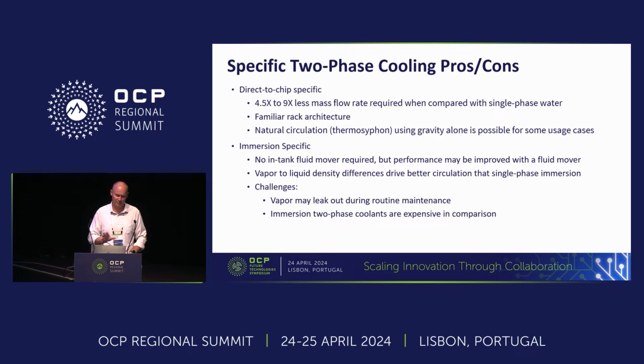Next, I want to go over some specifics on two-phase cooling pros and cons, first addressing direct-to-chip. One of the pros is much lower mass flow rates. Recall the discussion of latent heat versus sensible heat: when you run the numbers to remove the same amount of heat, you ultimately need 4.5 to 9 times less mass flow rate with two-phase cooling compared to single-phase water, with all the benefits that come with that. We're also using a familiar rack architecture, similar to air and single-phase water.